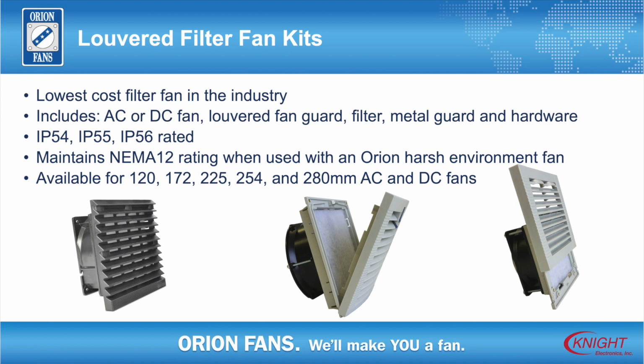Fans exposed to excessive amounts of heat and dirt fail at a rate much greater than those operating in normal environmental conditions. A dirty air filter can damage the fan motor by blocking the airflow, causing the internal motor temperature to rise. A fan motor operating above the ideal design temperature will cause the bearing to rapidly lose its lubricating properties, overheat, and fail. When combined with a louvered filter fan kit or an LFG series snap-on, slide, or hinge louvered guard, Orion Fans specialty air filters offer low pressure drop, water resistance, fire protection, and the ability to capture large amounts of airborne dust in industrial enclosure applications.